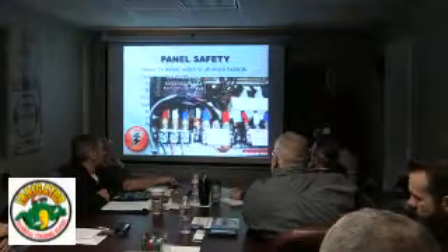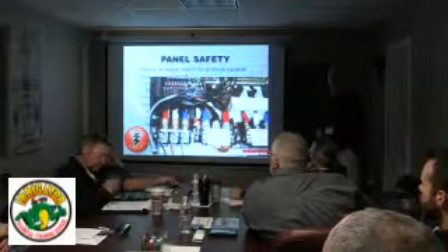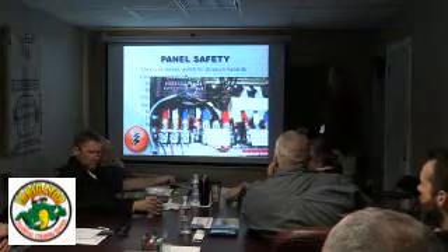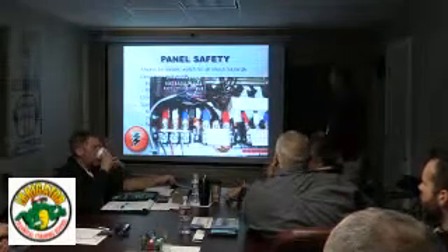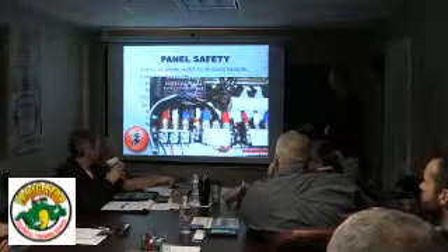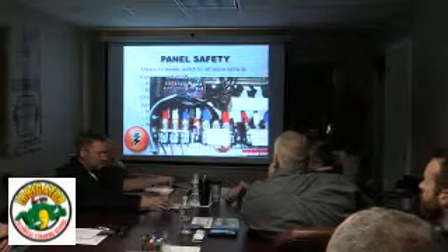So always be aware that a VFD drive can store that voltage on its DC bank for up to several minutes. Terry, a measure across the red and the black? Yeah, across the red and the black. Some might have a brake chopper or other options that would use this terminal. I think it is also still hot, but you would measure across the red and the black on DC volts.